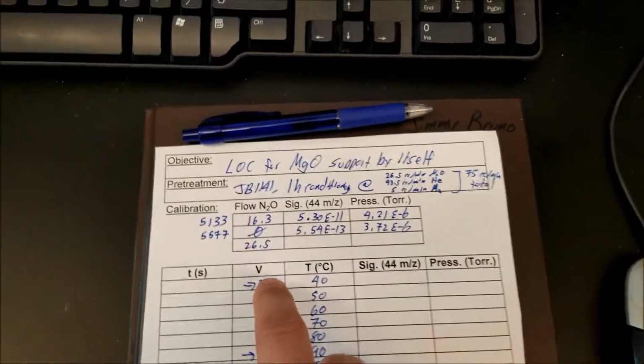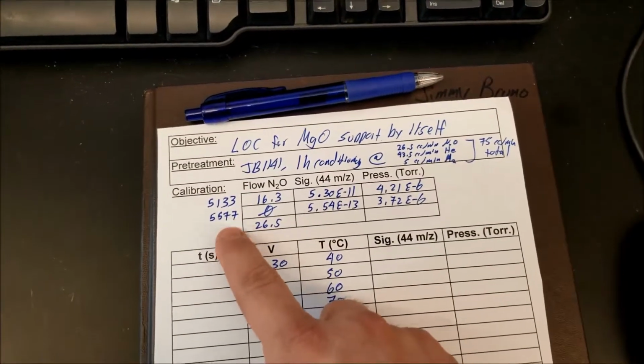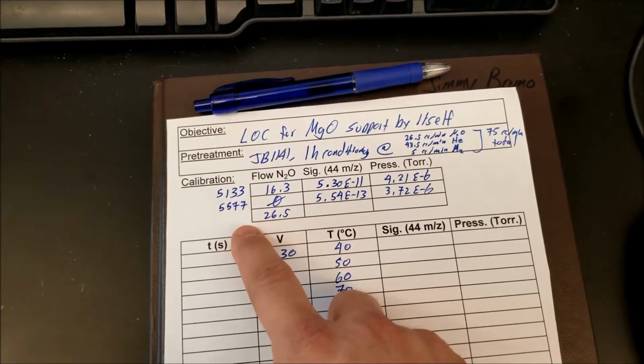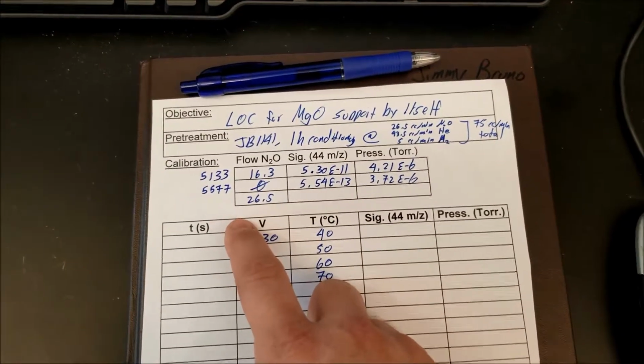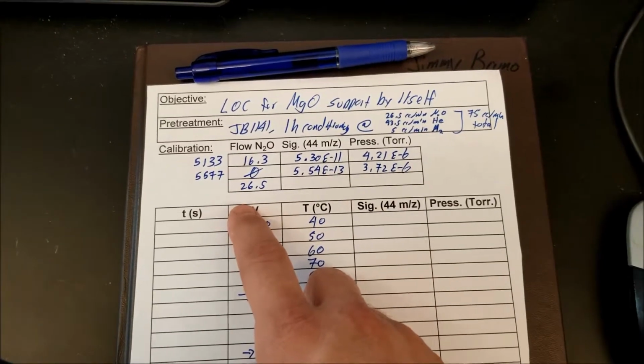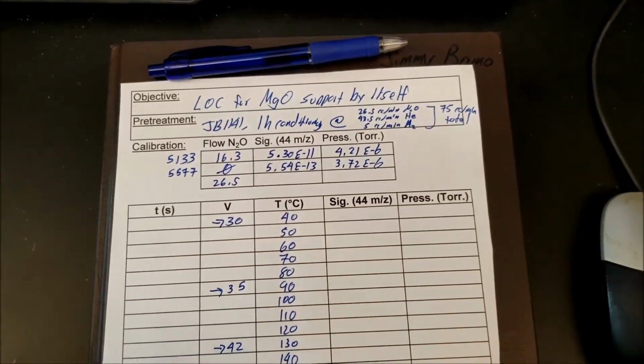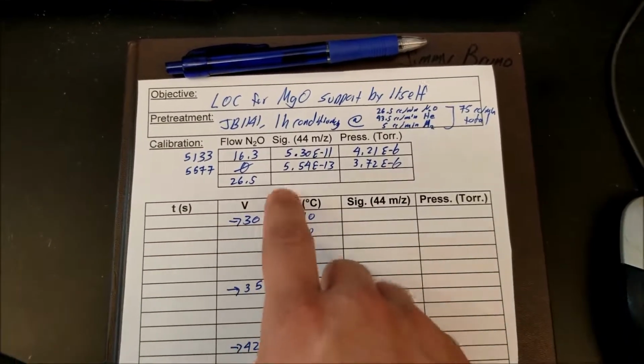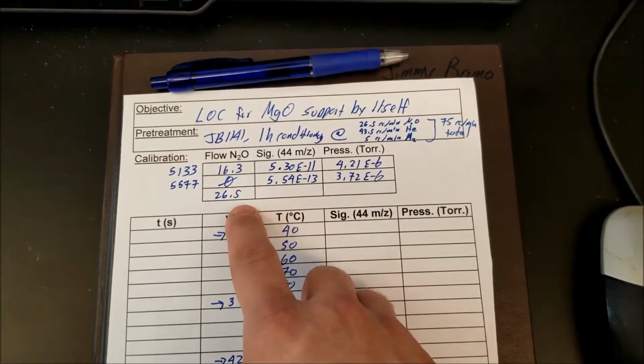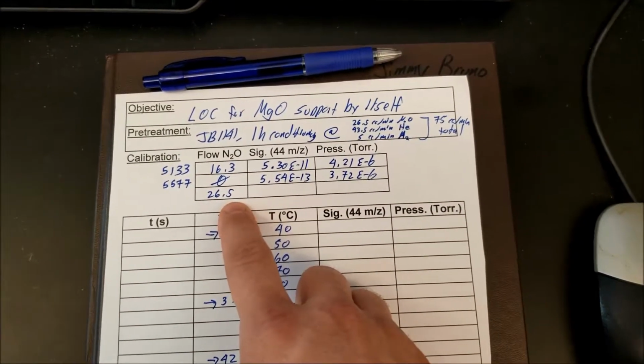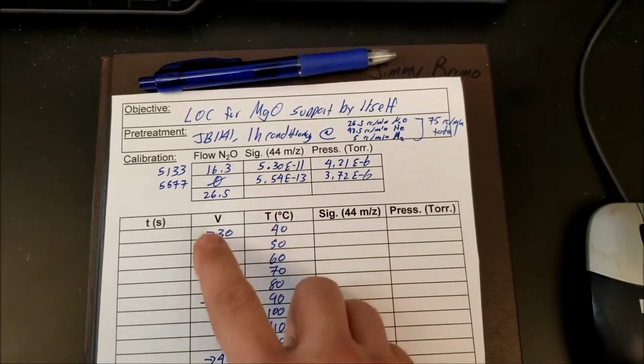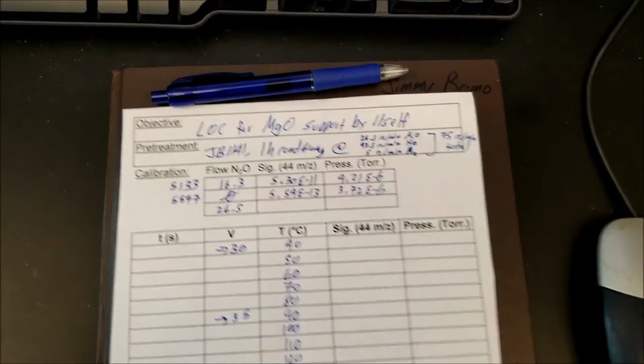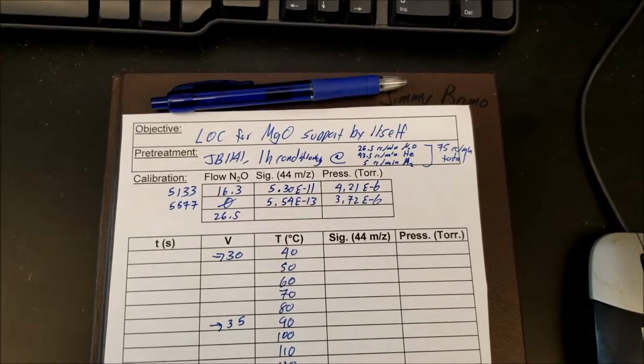So it's a bit of an oversight on my part. I don't have a time here. I'll have to add that into future printouts. But I usually test these in this order for the calibration. You can do it in a random order, but I think it's most beneficial that the sample point itself, or at least the sample flow rate that we're going to use for the test, the same one that we use for the conditioning, is the last point, because then we just get to turn the bypass and start the test.